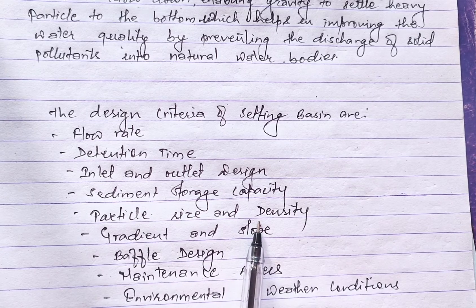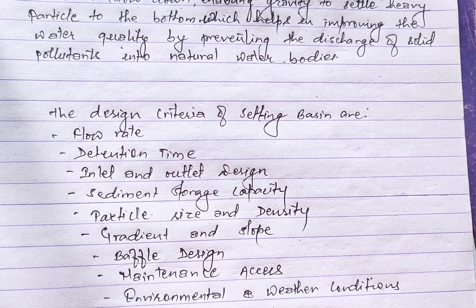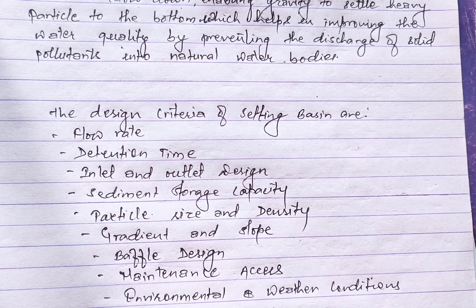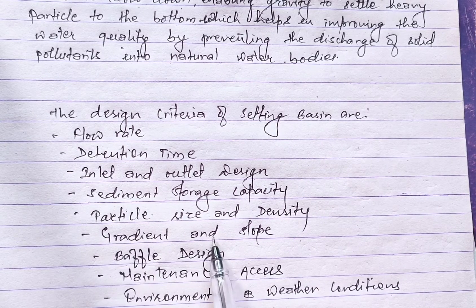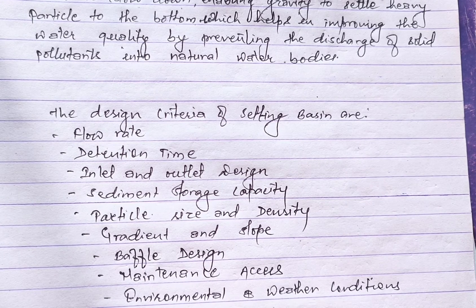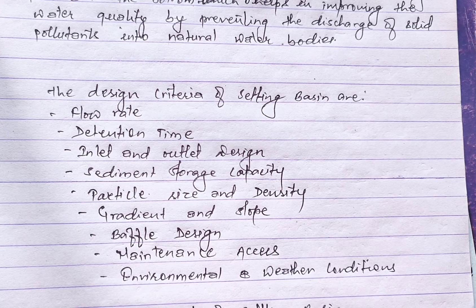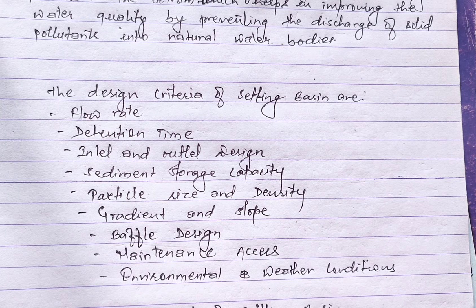Consideration of the characteristics of suspended solids, including particle size and density, is vital. The design should be tailored to efficiently capture specific particles present in the water. The basin's gradient and slope affect the settling process, and these parameters should be optimized to increase sedimentation without causing short-circuiting. Baffles within the basin help control the flow path, enhance settling time, and prevent short-circuiting, ensuring uniform distribution of flow.